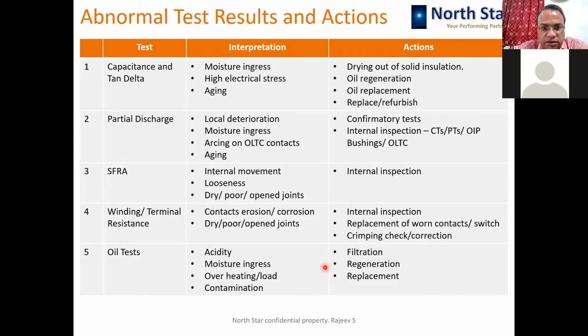SFRA test results indicate internal movement, looseness in the winding or in the clamping arrangement, or some lead has got open, or some joint has broken, the lead is broken. So it calls for the internal inspection. So after SFRA, the transformer is to be internally inspected. And if some looseness or something is found, then it is to be corrected.